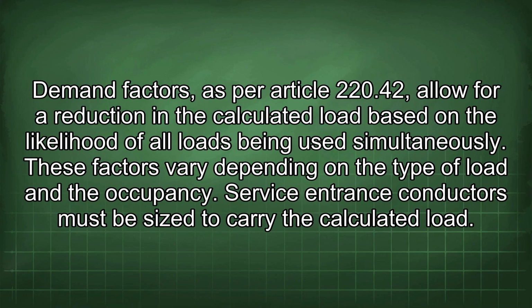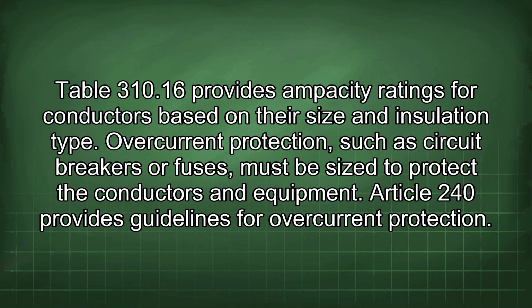Demand factors, as per Article 220.42, allow for a reduction in the calculated load based on the likelihood of all loads being used simultaneously. These factors vary depending on the type of load and the occupancy. Service entrance conductors must be sized to carry the calculated load. Table 310.16 provides ampacity ratings for conductors based on their size and insulation type.